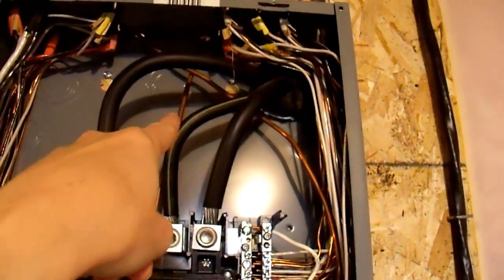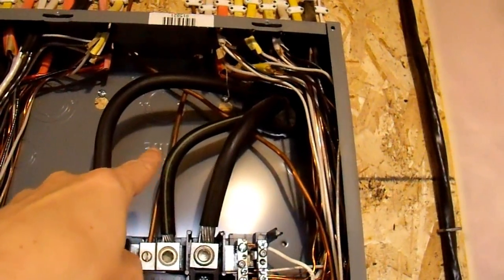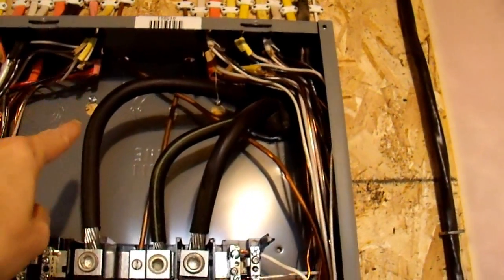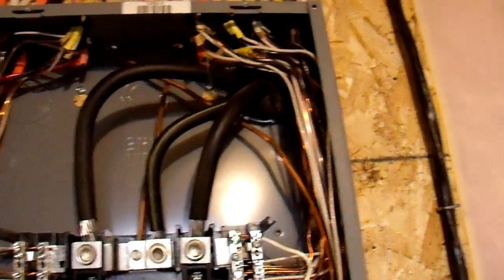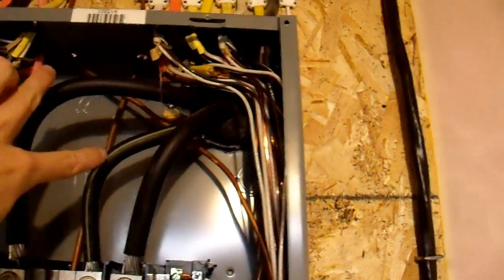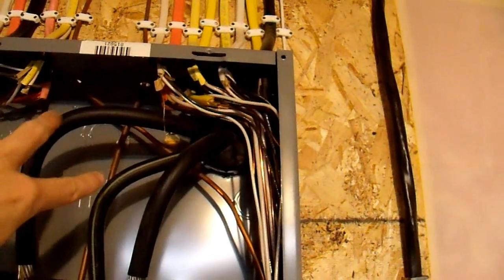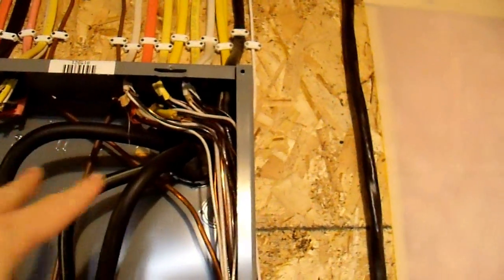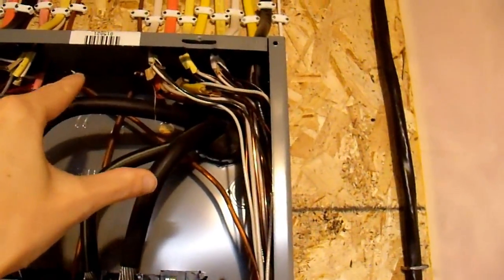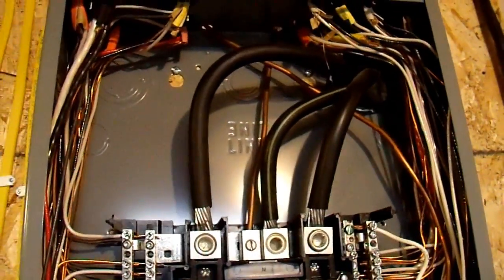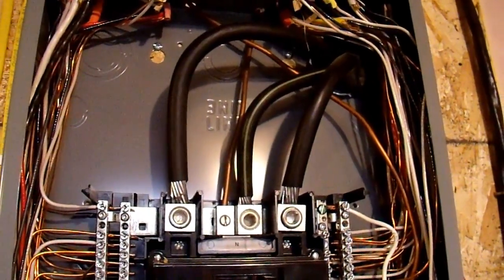So you need to turn this off. I'm not going to do that right now because it's dark and we'll be in the dark. But I also want to mention quickly how these are wired up. You have a single ground in the middle. That's a neutral, current-carrying neutral, and you have two phases. One here, one over here. Each one of these is 120 volts. So if you connect between these two lines, you get 120 volts. Connect between these two, you get 120 volts. If you connect between these two, you get 240 volts. And that's how you get the two voltages in your house.